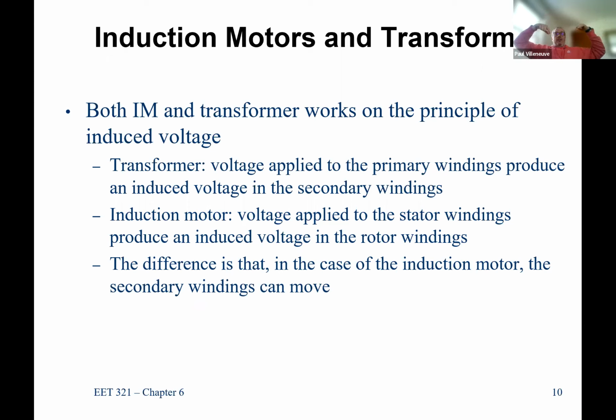So can you think a little bit about how an induction motor is taking a real beating when it's not rotating, because remember that rotor winding is short circuited. So if you didn't allow the motor to rotate, if you locked it in position, you would burn it up, because you're moving all this power from a primary to secondary, and you have a short circuit in the secondary, so you would generate a lot of heat. So one of the things you see is under blocked rotor conditions, you have to do motor protection, because you will burn up your motor pretty quickly.